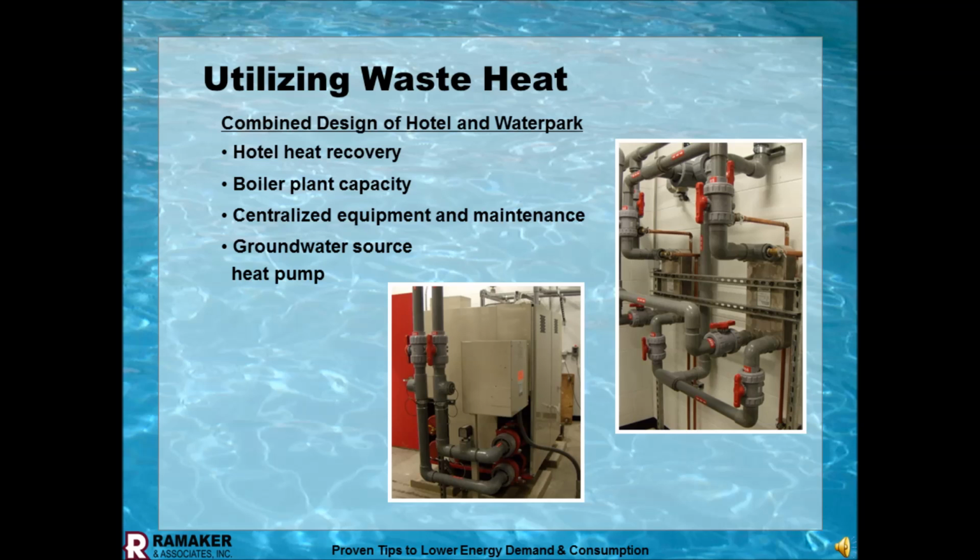So they were using geothermal energy to heat the buildings, and the heat pump was running a water loop throughout the whole campus. Down in the classrooms they're generating heat, in the pool they need heat, and they're just transferring heat around. And they're using the groundwater as a heat sink, or to heat the buildings in the wintertime.